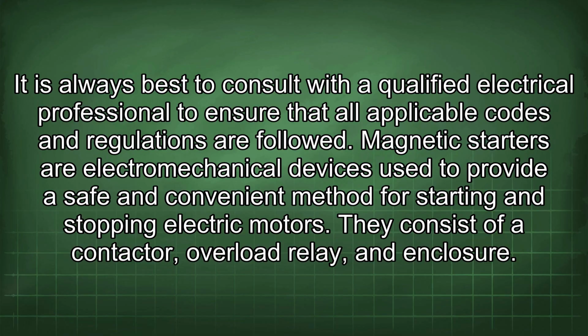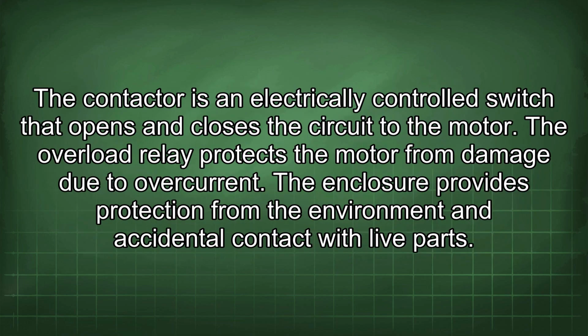Magnetic starters are electromechanical devices used to provide a safe and convenient method for starting and stopping electric motors. They consist of a contactor, overload relay, and enclosure. The contactor is an electrically controlled switch that opens and closes the circuit to the motor. The overload relay protects the motor from damage due to overcurrent. The enclosure provides protection from the environment and accidental contact with live parts.